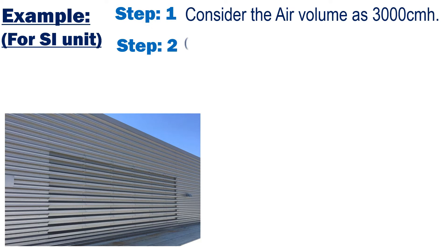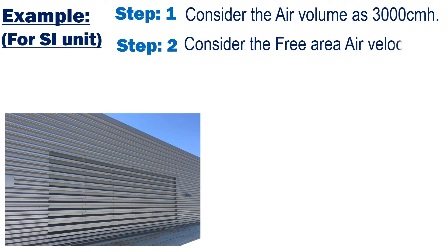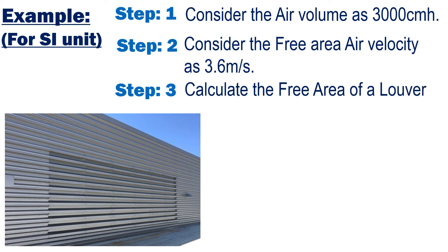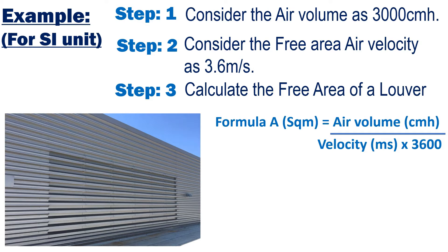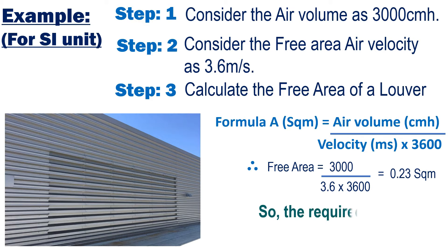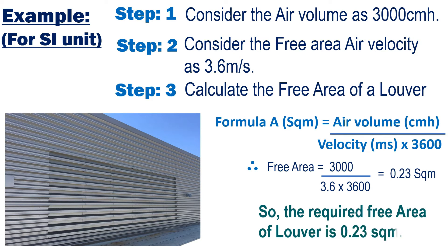Step 1: consider the air volume as 3000 cubic meters per hour. Step 2: consider the free area air velocity as 3.6 meters per second. Step 3: calculate the free area of the louver. The formula is: Free Area (m²) = Air Volume (m³/hr) ÷ Velocity (m/s) × 3600. Therefore, Free Area = 3000 ÷ 3.6 × 3600 = 0.23 square meters. So the required free area of the louver is 0.23 square meters.